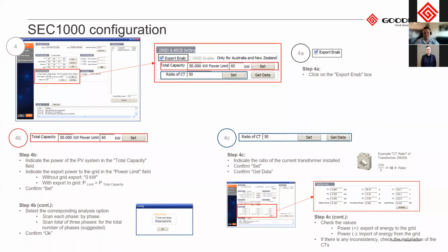Then lastly, we're going to go to number 4C, which is our CT ratio. So yeah, we just have to calculate our CT ratio. We don't put the actual ratio number in here. Since we always use 5 amp ratio CTs on this device, we don't use any of our GoodWe provided CTs. The CT90s or the normal GoodWe smart meter CTs, none of those CTs work on this because they are not 5 amp ratio CTs. We have to use just normal standard 5 amp current transformers.